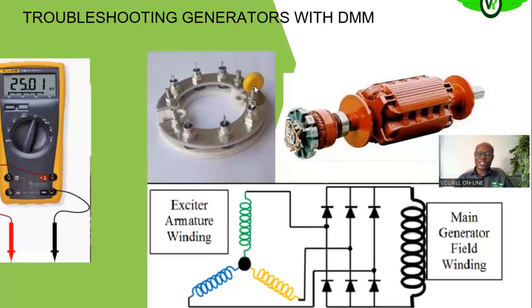So what this does is that once that excessive voltage comes, it will blow up and breach the phase and the neutral, meaning the positive and negative, so whatever voltage that was supposed to come to the main field will be shorted.